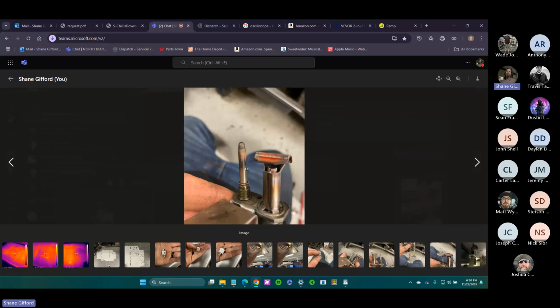Exactly the same thing as a flame sensor in any gas furnace. If you have a gas furnace that lights and immediately shuts off, or lights and runs for a couple minutes but then shuts off, clean the flame sensor. It's just good maintenance to have done at least once a year. In fact, I was talking with Nathan about it today. All of our Hotside customers, in my opinion, we should be offering them maintenance to go around and clean out their Hotside appliances, blow out the burners, make sure there's no soot or debris near the flames. A lot of times food can get dropped and sticks to the burners and cakes on there. This has to get cleaned, I would say, at least once a year.